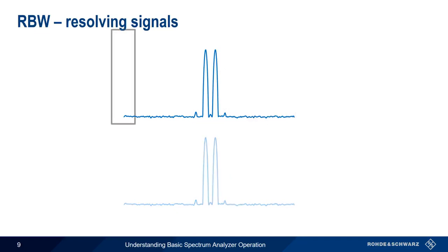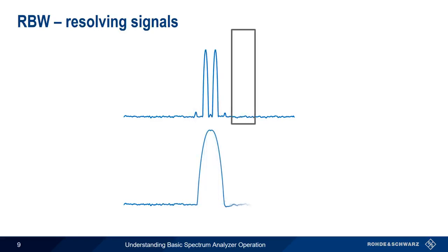If we were to use a wider resolution bandwidth, both tones are covered by the filter as it sweeps past, and they appear as a single signal in our trace. The other important aspect of resolution bandwidth is the effect that it has on noise. More specifically, resolution bandwidth affects the noise floor, also referred to as the Displayed Average Noise Level, or DANL.